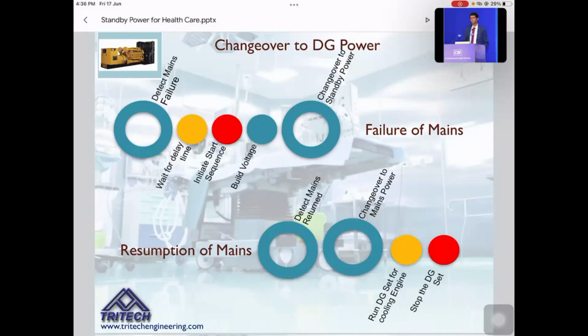So the switching off sequence includes a no load operation, no load running, and only then does the generator shut off. So this is the start and stop sequence during failure and resumption of the mains.